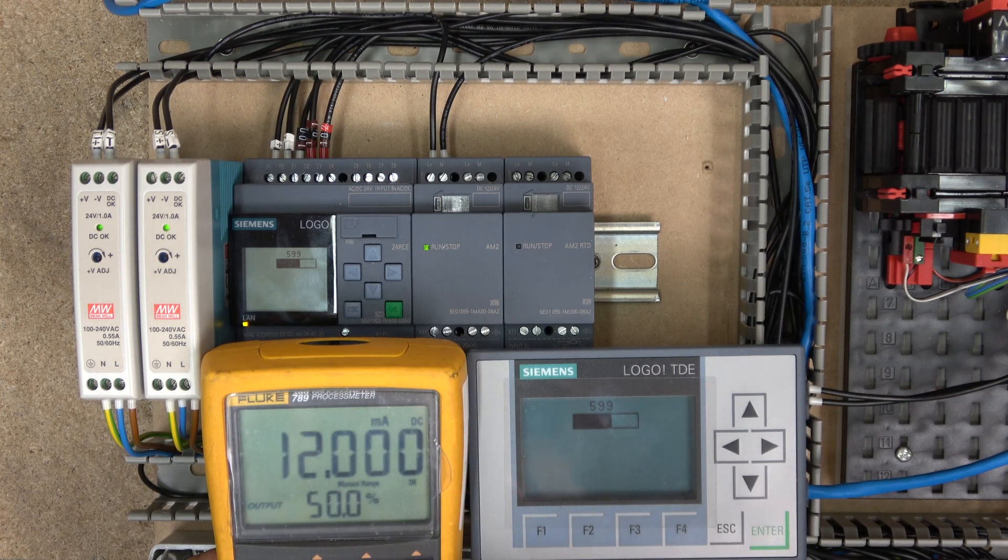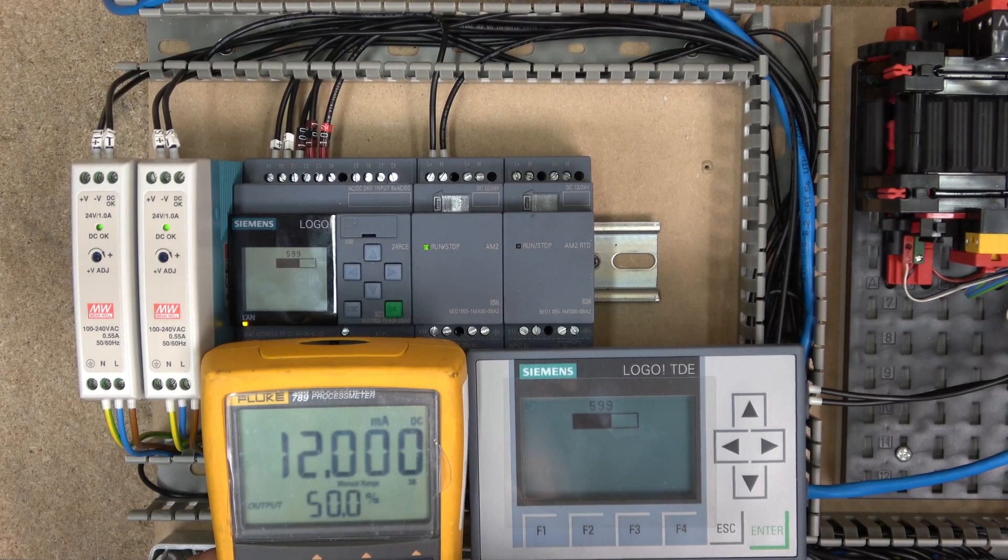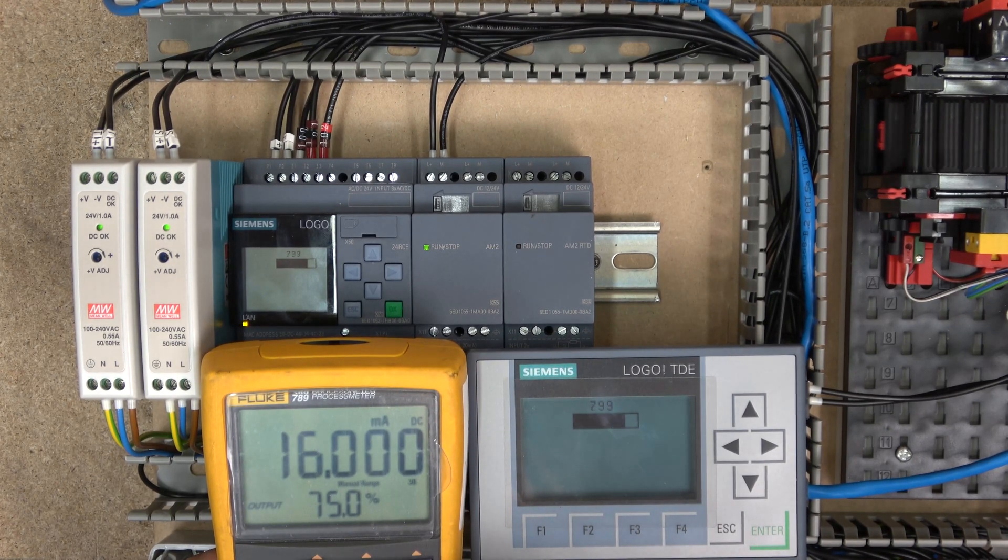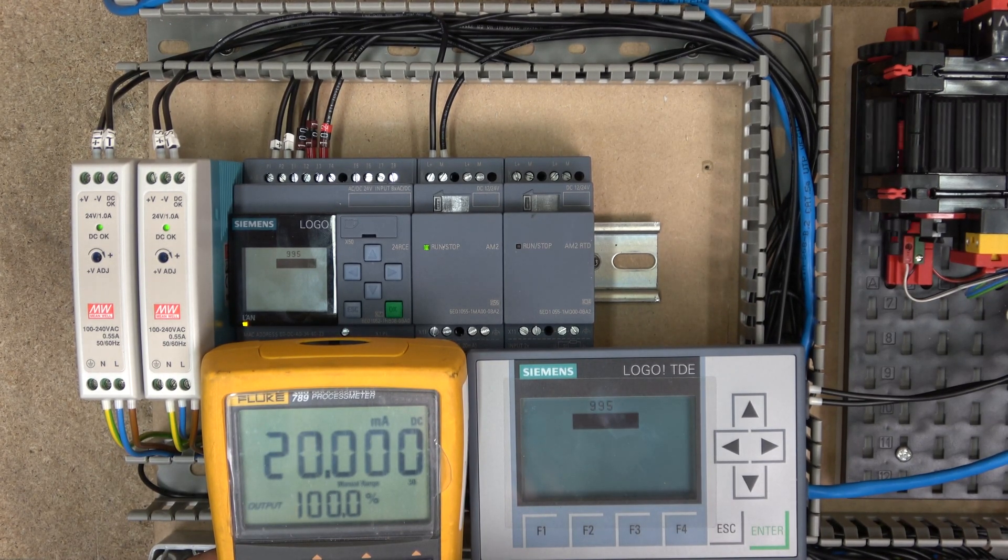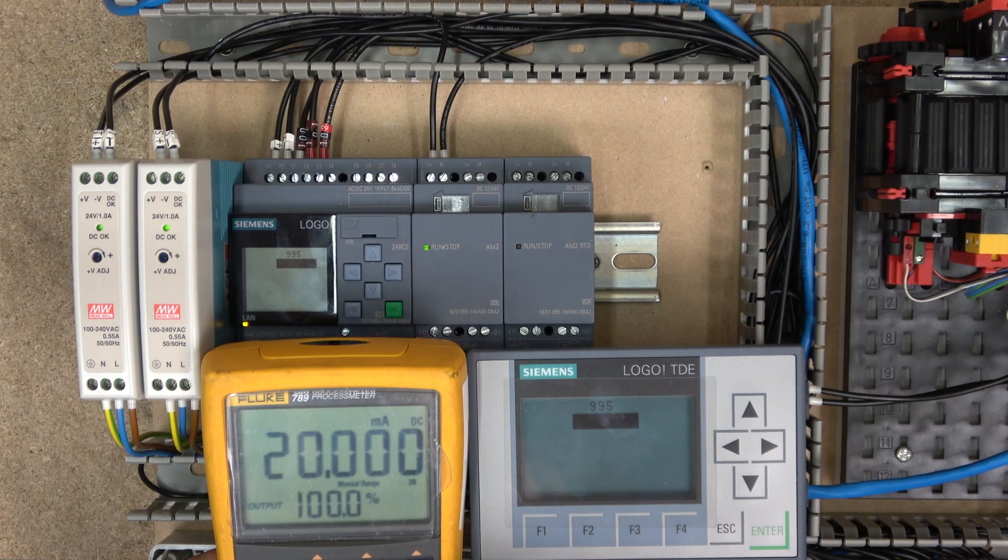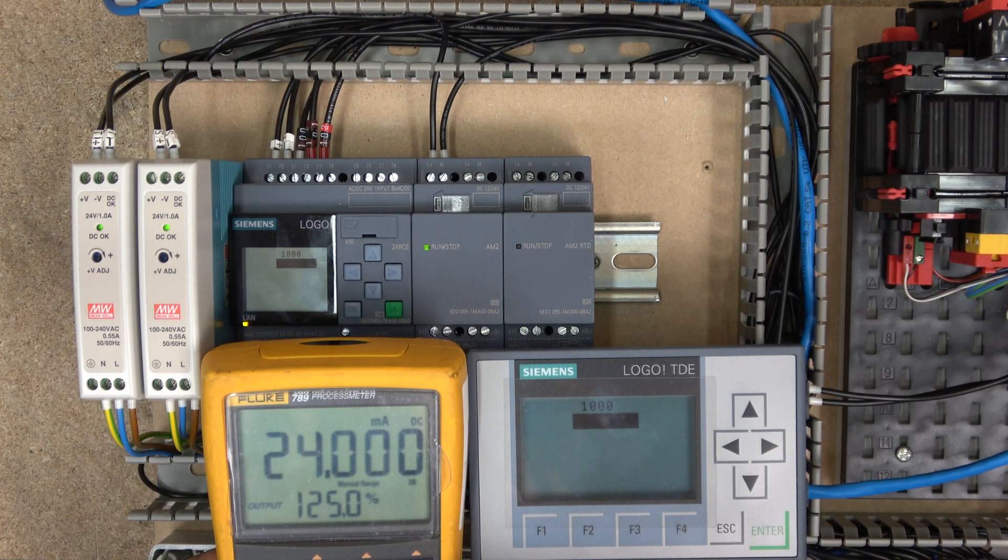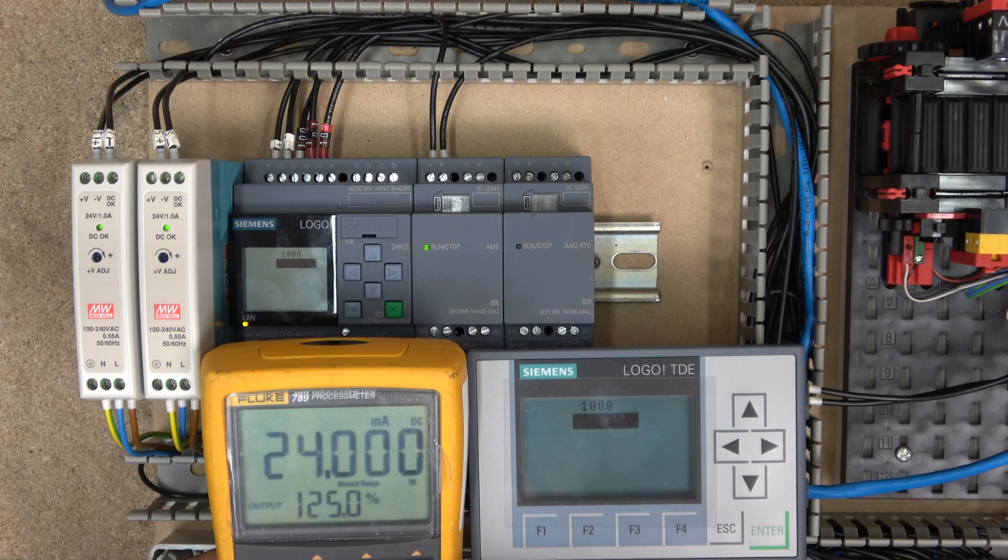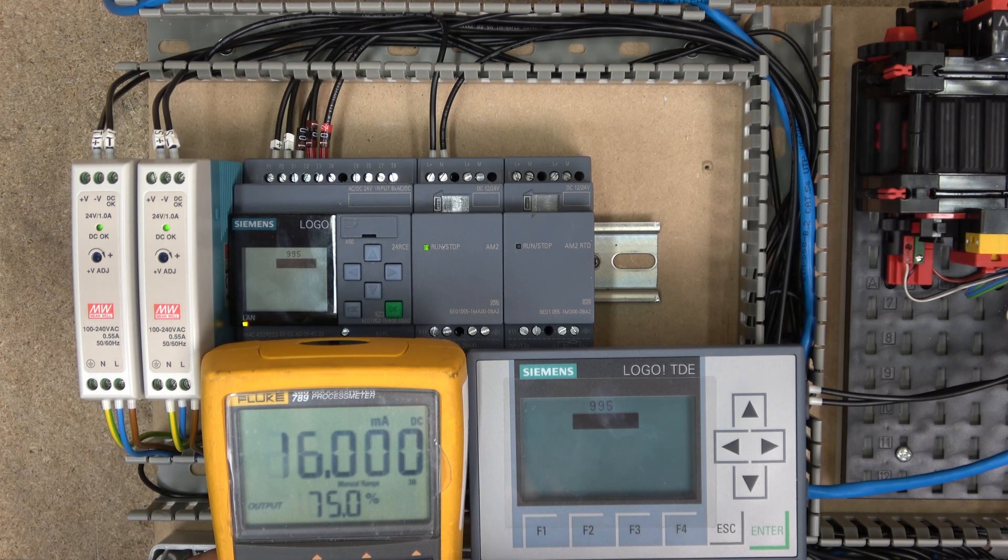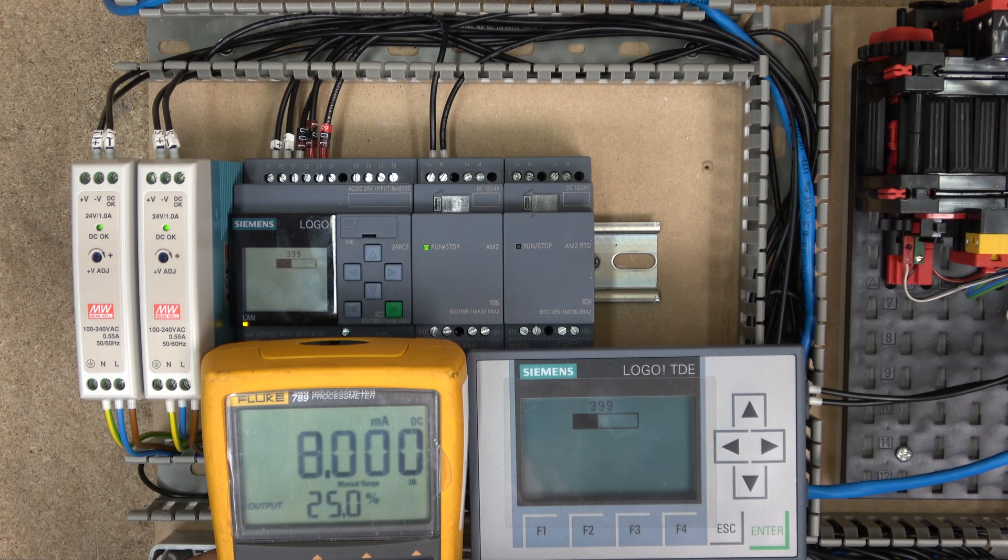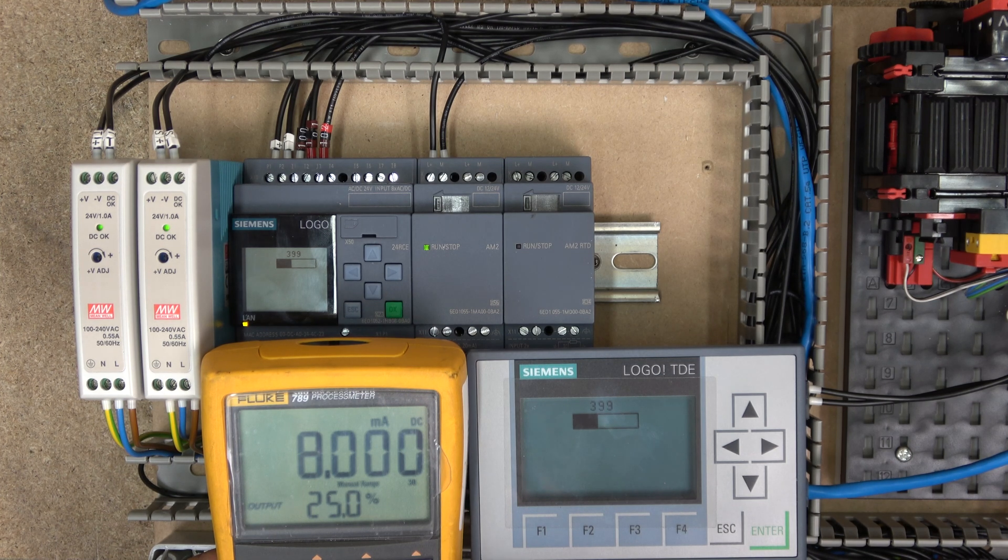That could be anything, pump or whatever you can come up with. So as you can see, it goes all the way to 1,000. If I go higher than 24 milliamp, it doesn't do anything. It just stops at that. So here we go. And as you can see, we'll go below. It went below to 450 and it shut the system down.